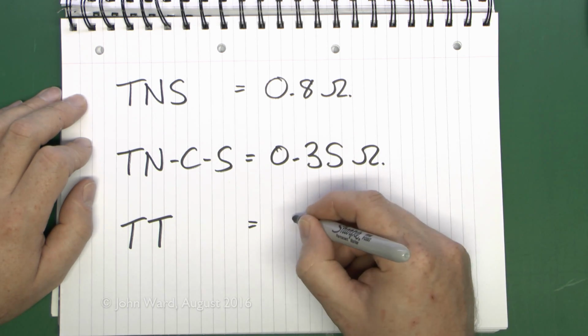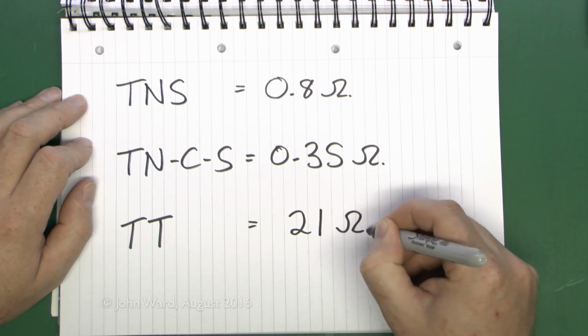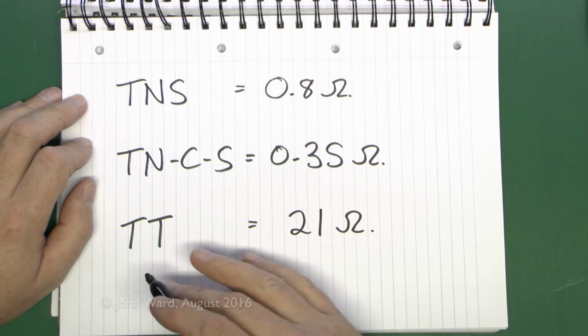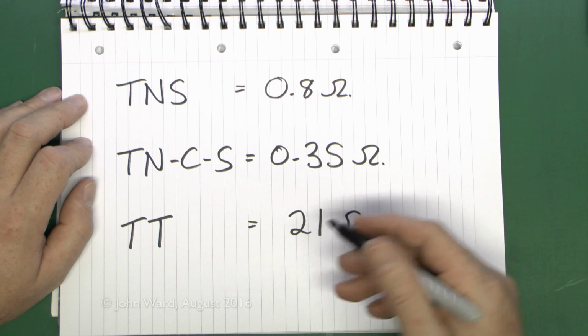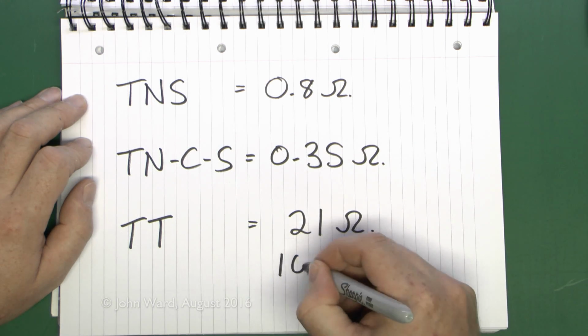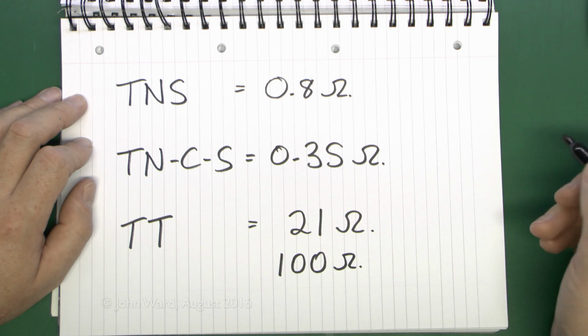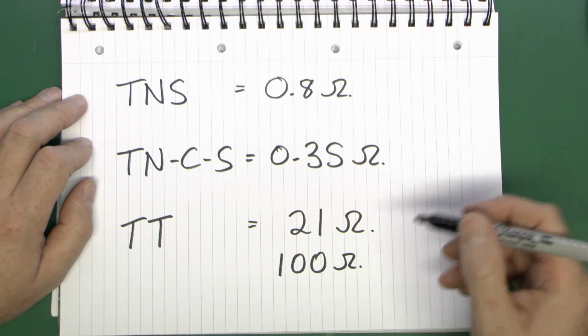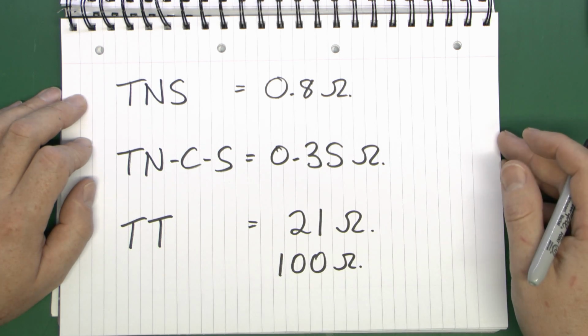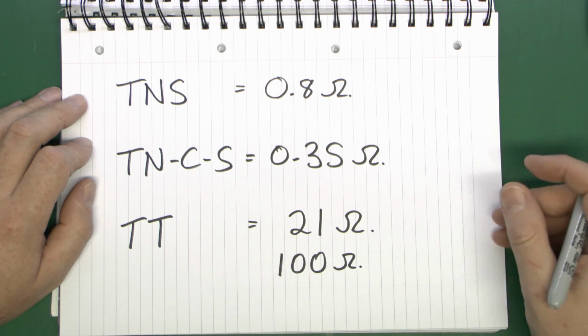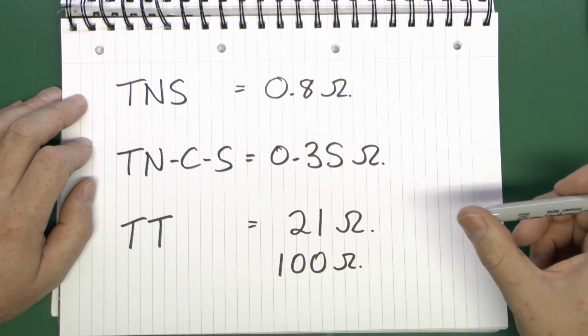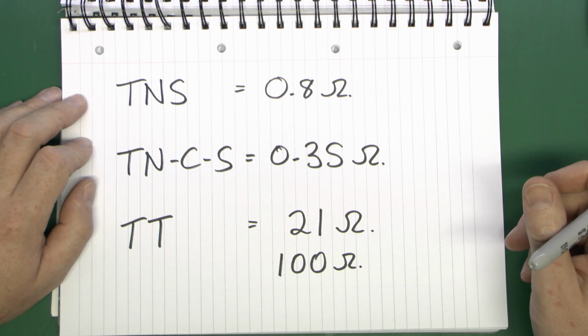In theory, you could get one in the region of 21 ohms, which is partly due to how things are installed at the substation. But in the real world, you're probably looking in the region of anything up to 100 ohms or so. Anything above 100 ohms generally requires some investigation, and certainly if it was in the 200-300 ohms range, that would generally not be considered acceptable.